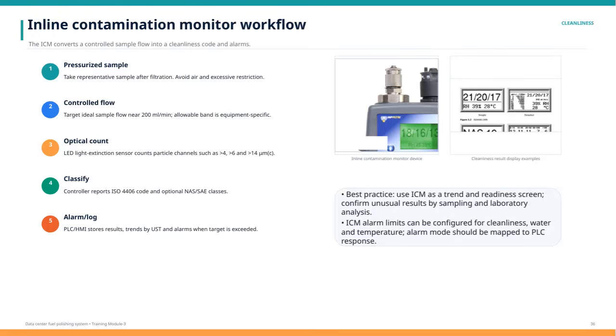Here we have an overview of the inline contamination monitor workflow. The monitor works by converting a controlled sample flow into a cleanliness code and alarms to keep us informed of fluid quality in real time. First, a pressurized sample is taken after filtration. It's important to ensure the sample is representative by avoiding any air bubbles or excessive restrictions that could skew the results.